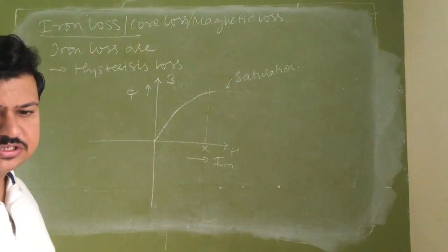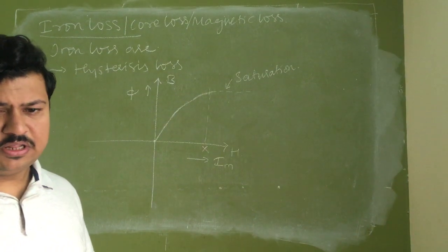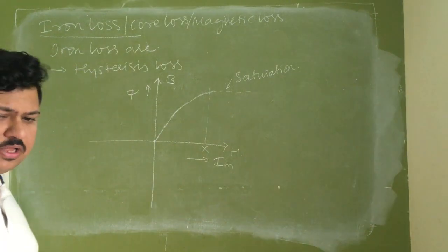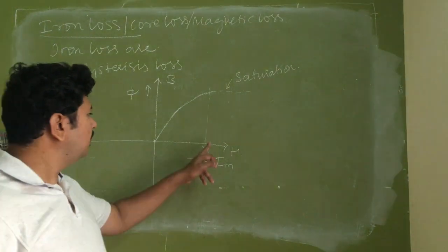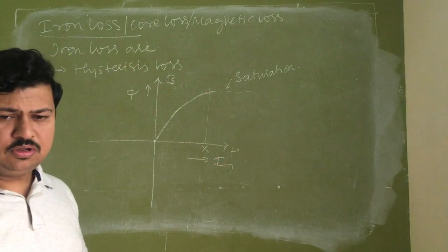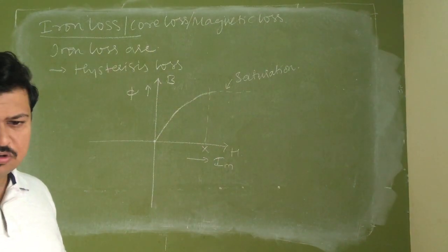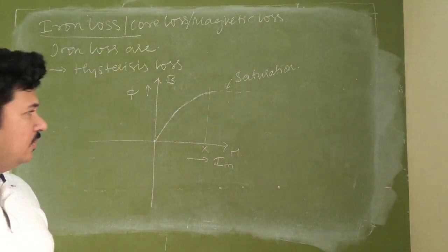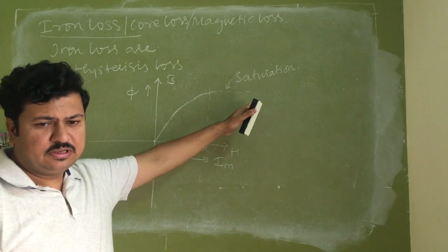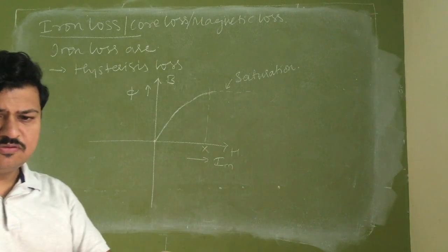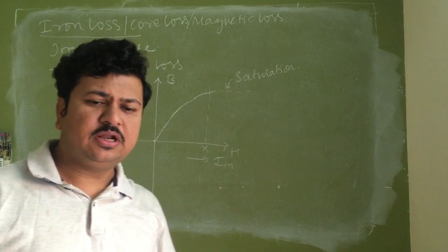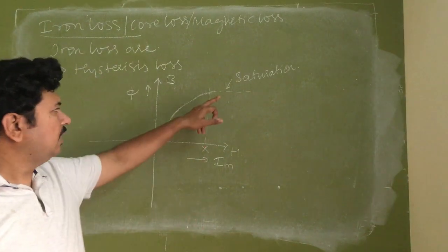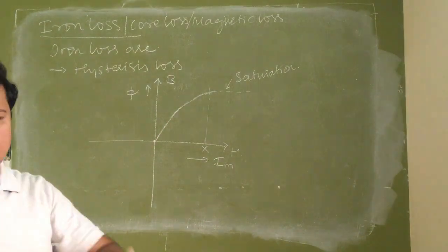This is called saturation of magnetic material. Now never, for any electrical machine, should I go beyond the point X. No electrical machine should go into saturation of magnetic parts, because once saturation is reached, the rate of change of flux is zero, hence the energy transferred or converted becomes zero. So the magnetic parts in an electrical machine should never get magnetically saturated.